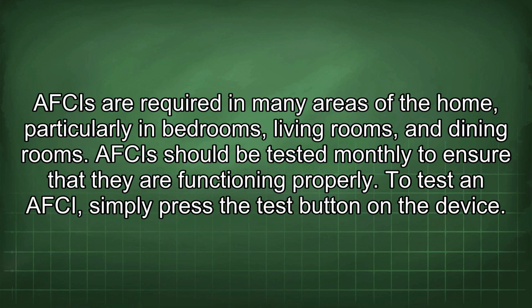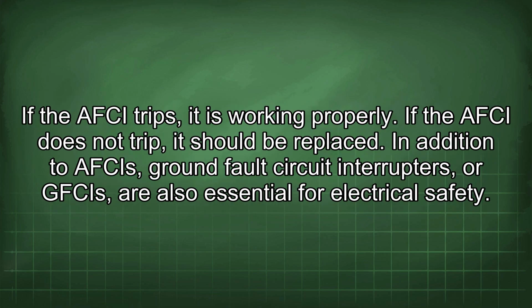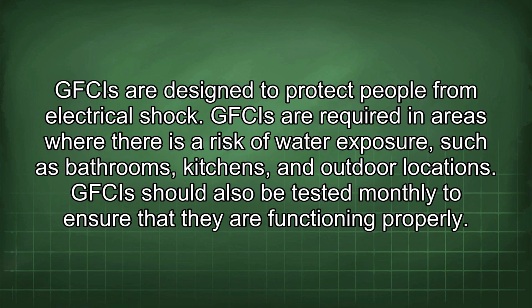To test an AFCI, simply press the test button on the device. If the AFCI trips, it is working properly. If the AFCI does not trip, it should be replaced. In addition to AFCIs, ground fault circuit interrupters, or GFCIs, are also essential for electrical safety. GFCIs are designed to protect people from electrical shock. GFCIs are required in areas where there is a risk of water exposure, such as bathrooms, kitchens, and outdoor locations.